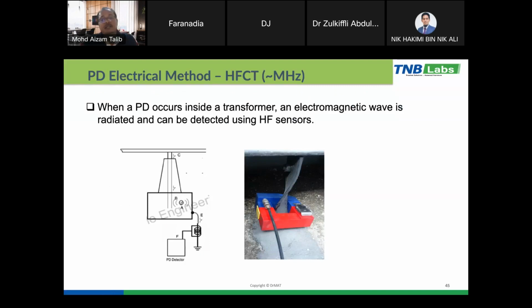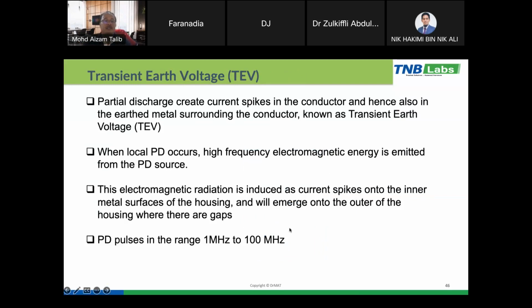And then for the electrical method, we can also use HFCT, high frequency CT. This is called non-conventional. IEC 60270 is considered conventional PD testing, but other than that, we call it non-conventional. For example, we use the CT, where we put it at this ground terminal, or at this conductor, or the neutral conductor. The theory is that when a PD occurs inside the transformer, it will generate an electromagnetic wave, and this electromagnetic wave will radiate and travel to the ground. So when we clamp the HFCT at this ground terminal, we are able to detect the pulse currents.